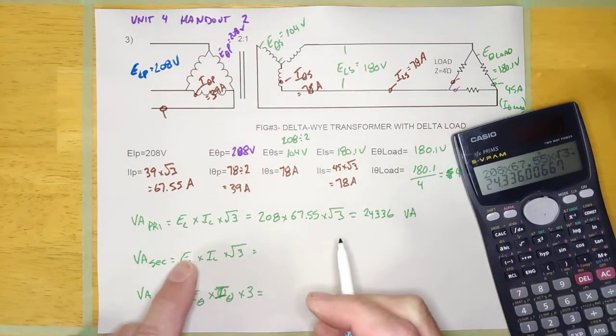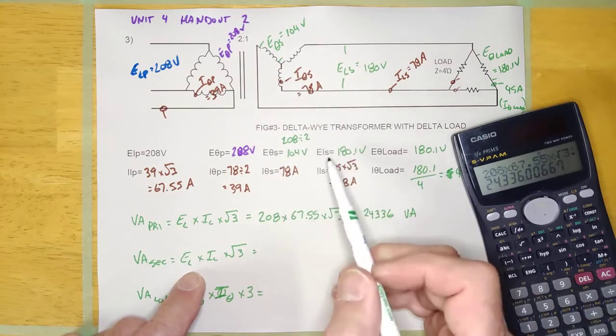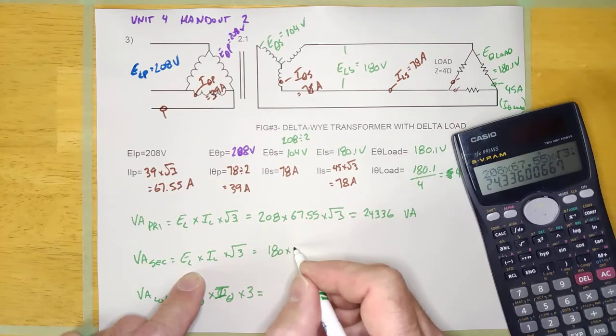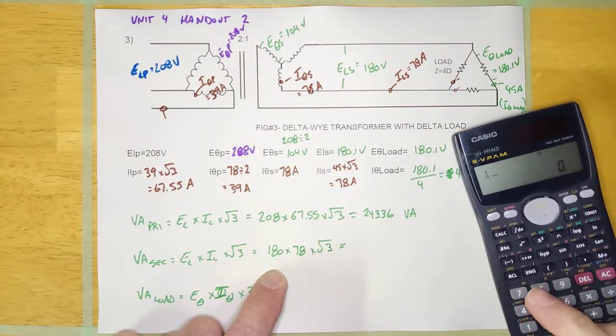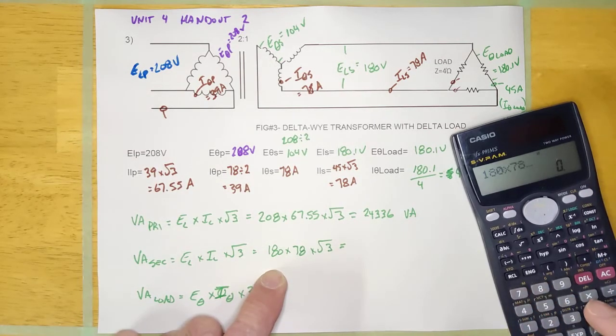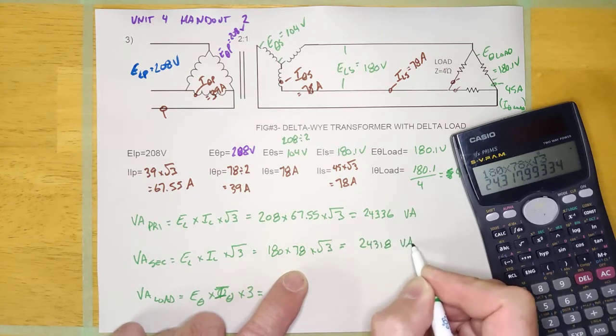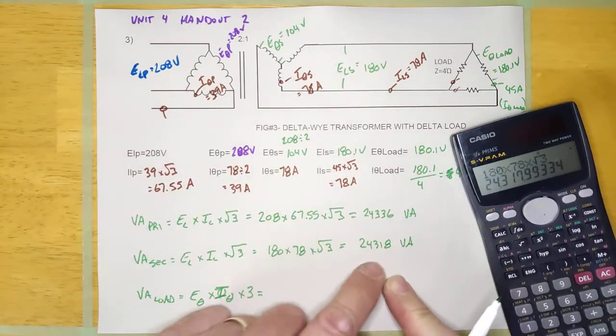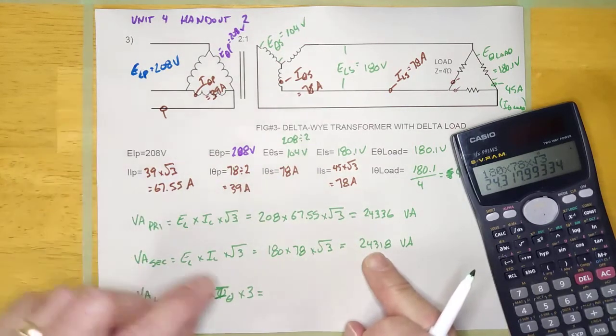Let's check it at the secondary the same way with line values. E-line secondary is right here. So: 180 times 78 times √3 equals 24,318 volt-amps. Notice that they are essentially the same — the small difference is just rounding. Both come out to approximately 24.3 kVA.